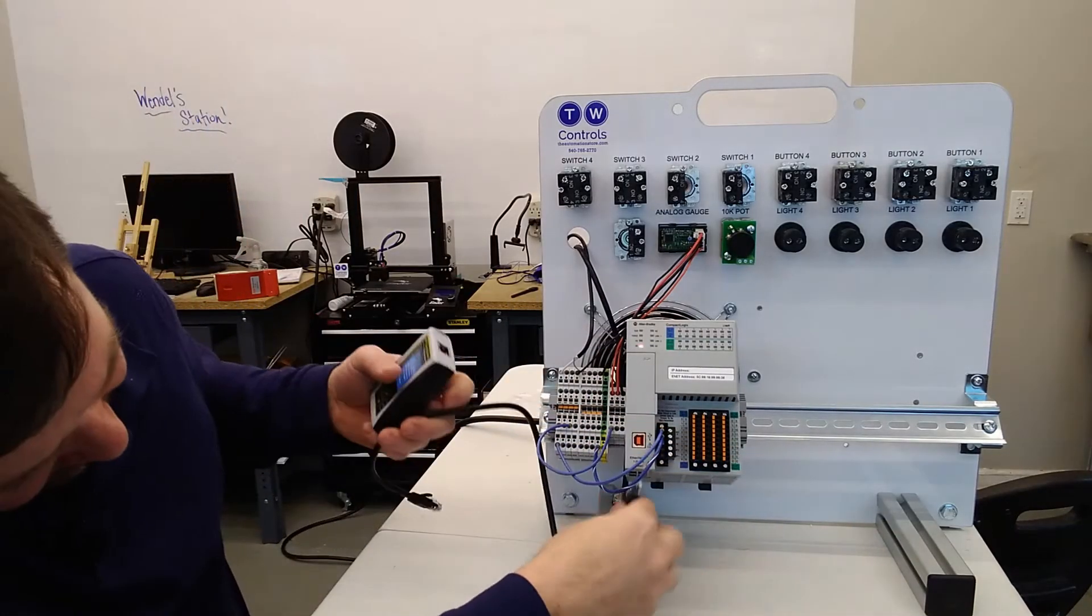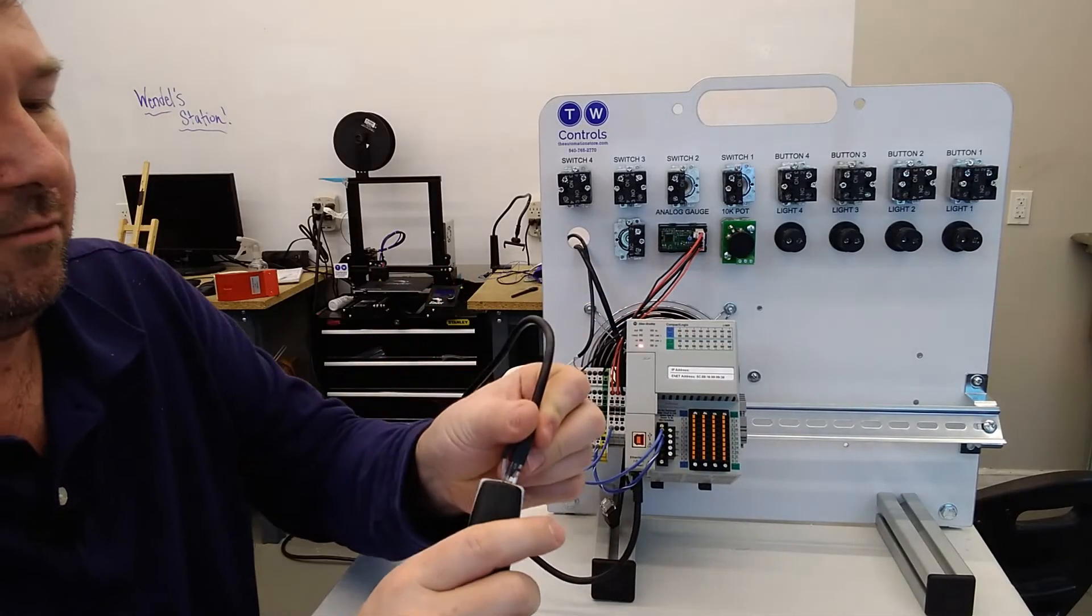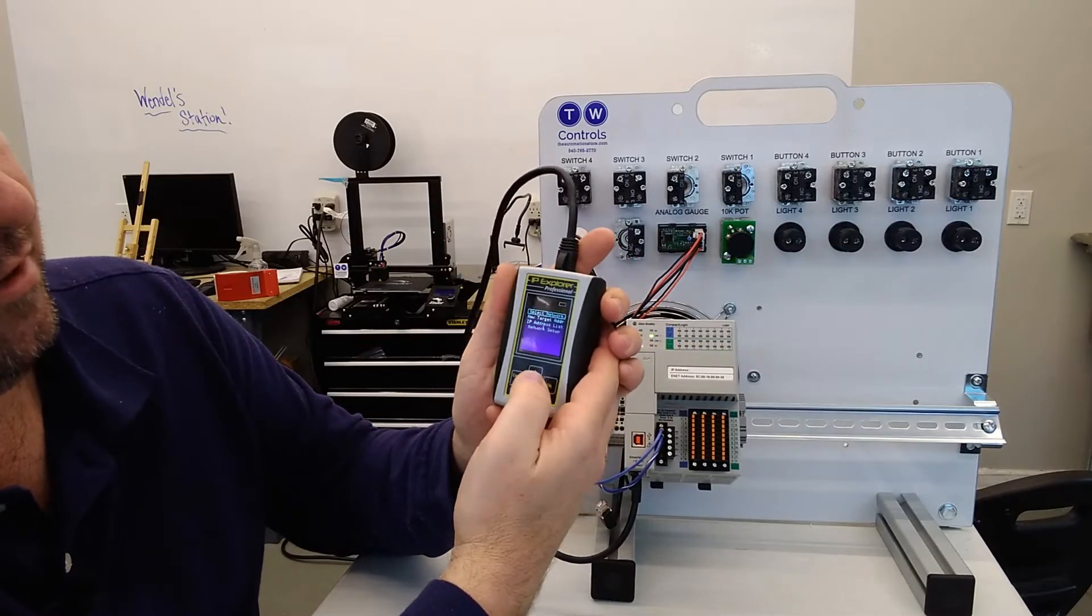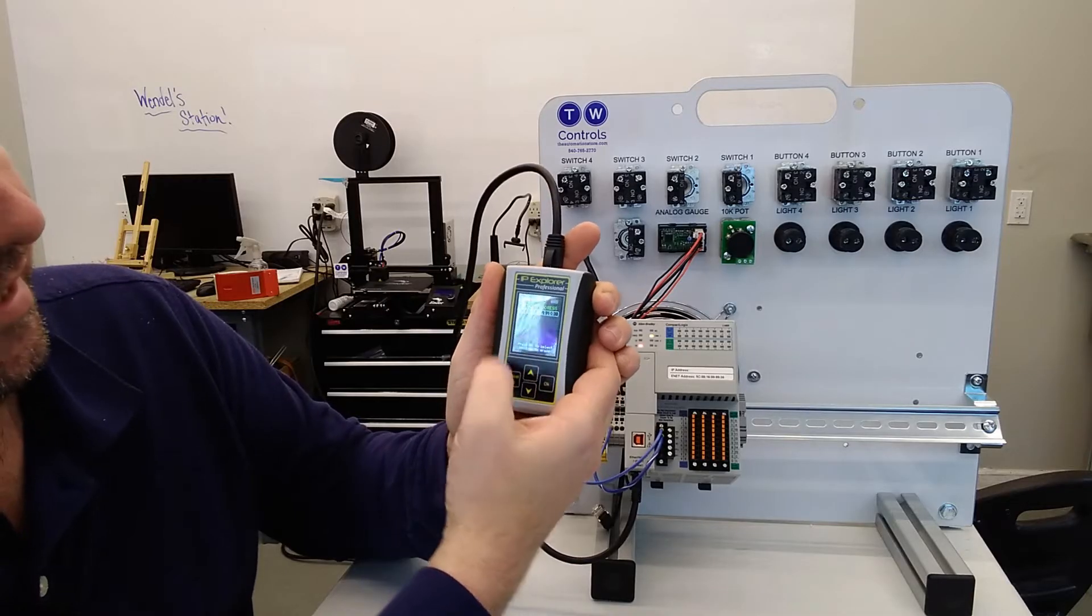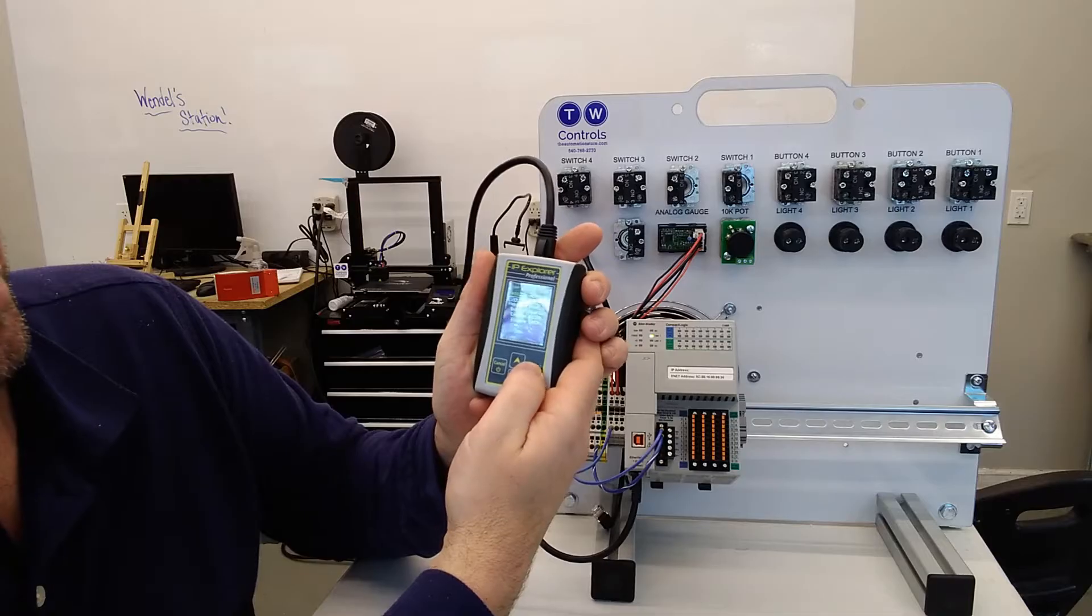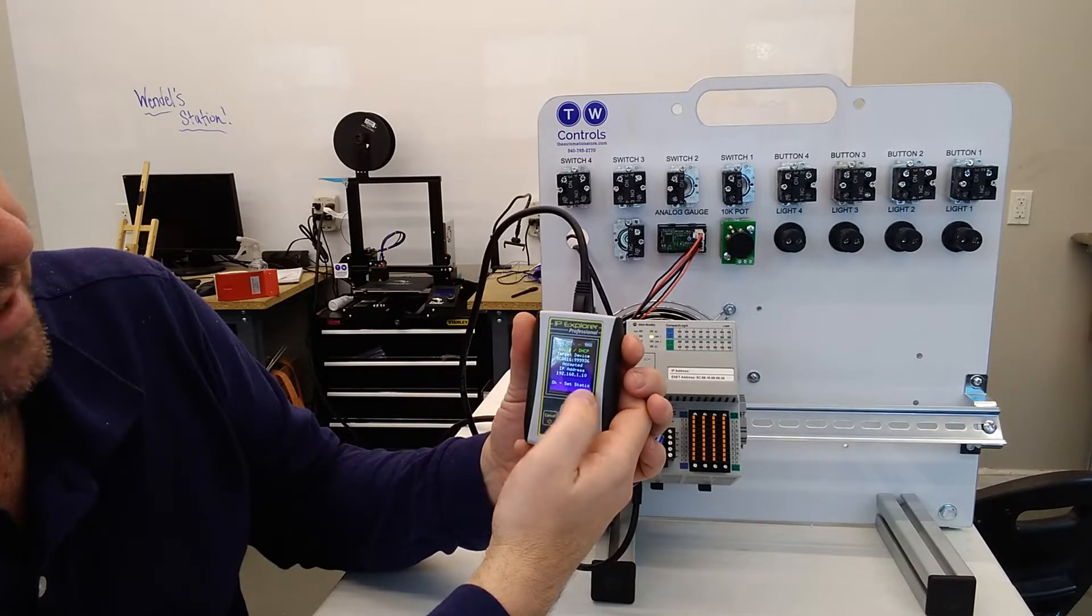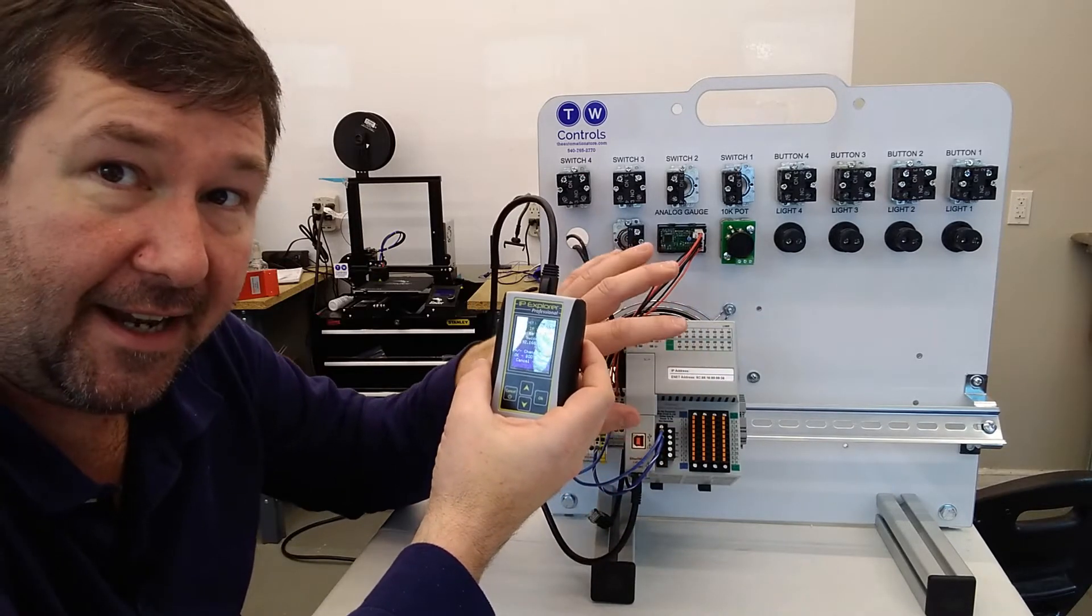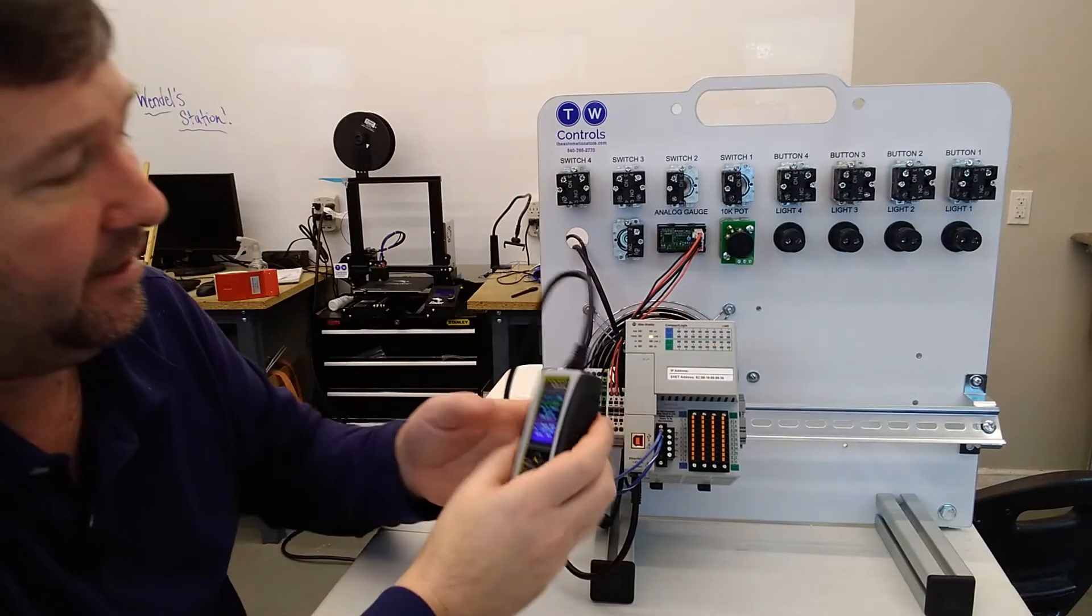We're just going to plug into the Compact Logix. Then we're going to go to prepare IP address. I already have it configured for 192.168.1.10. Then we're going to go to assign address and use BOOTP/DHCP, and it's set it. And then we're going to press OK to set it to static. That makes it where permanently that has an IP address of 192.168.1.10.